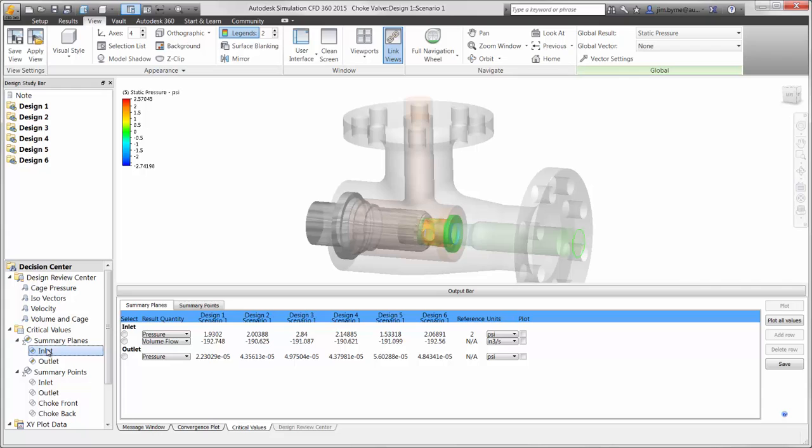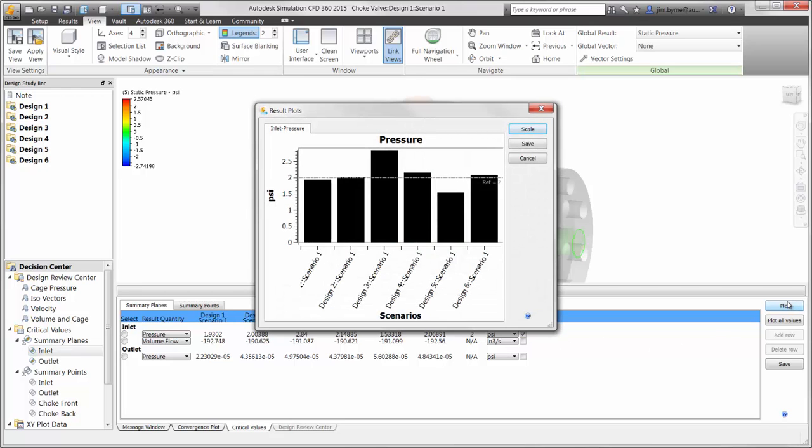Summary information can also be saved from the section planes or probe points for comparing maximum values. Taking a look at the values for pressure drop, we can see there are a couple of caged designs that are below our requirement of less than 2 psi. Design 5 is performing the best in this area.